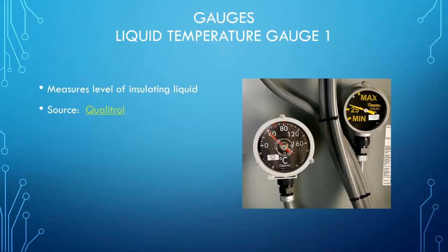Here are some liquid temperature gauges, and these measure the temperature of the actual fluid. There's also a gauge that I did not mention here that we call a winding temperature gauge. That actually comes from RTDs in the actual windings.